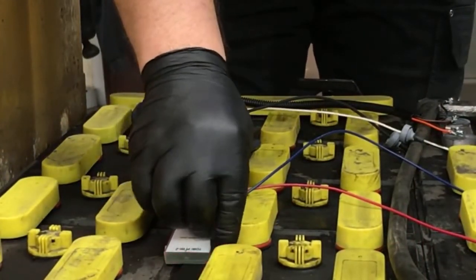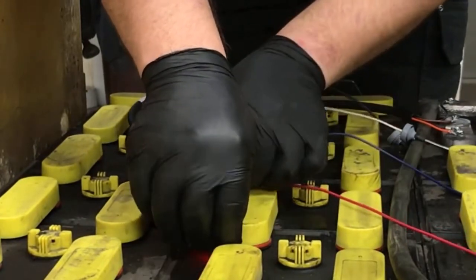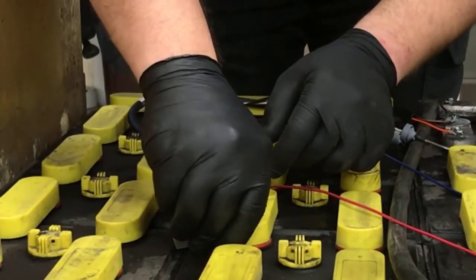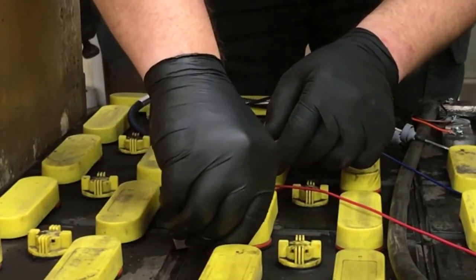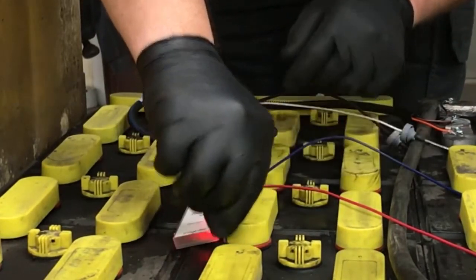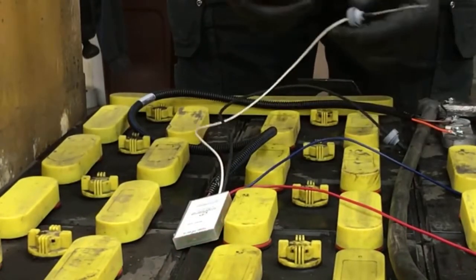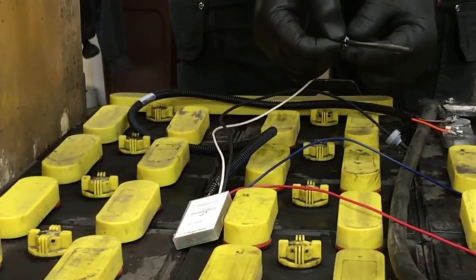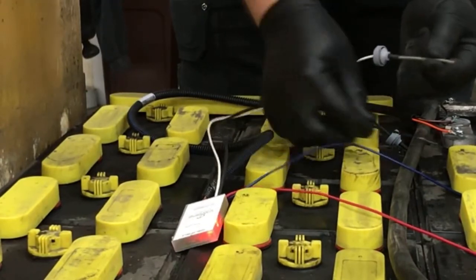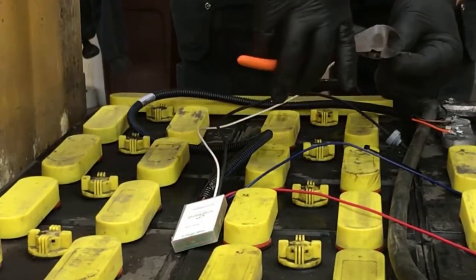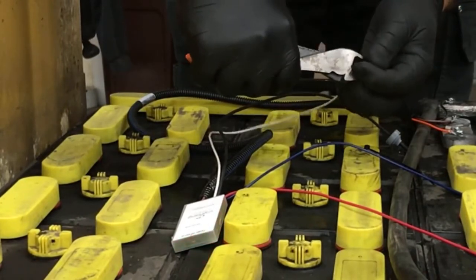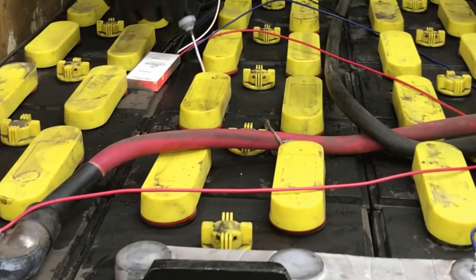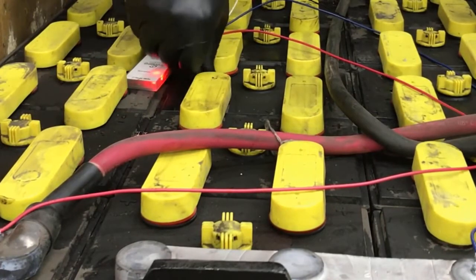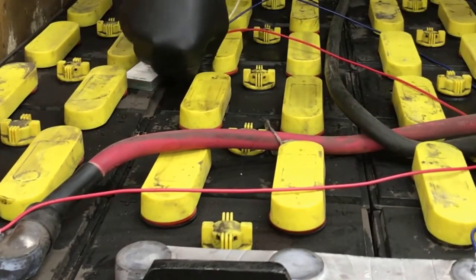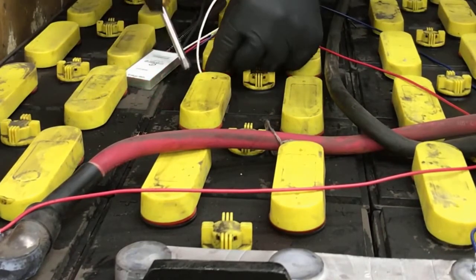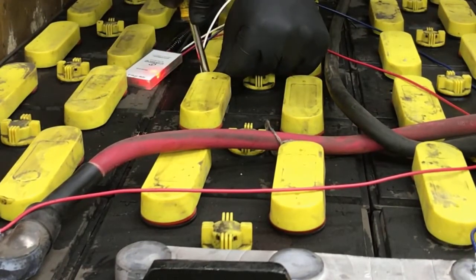Using one of the plastic cable ties, measure the distance from the top of the cell to the moss shield. Trim the water probe to a length approximately 1/8 inch above the moss shield. Insert the water probe through the hole in the top of the cell and press the grommet into the hole. Use a nut driver to press down on the edges of the grommet so that it's fully seated in the hole.